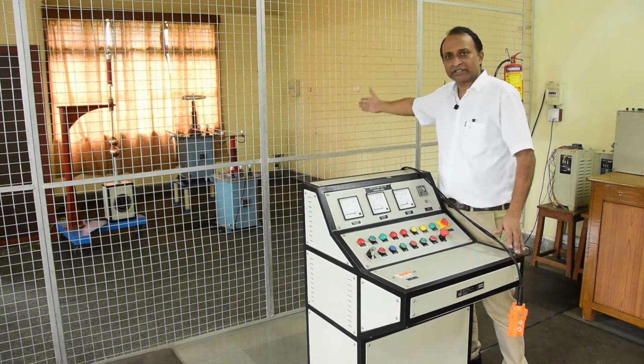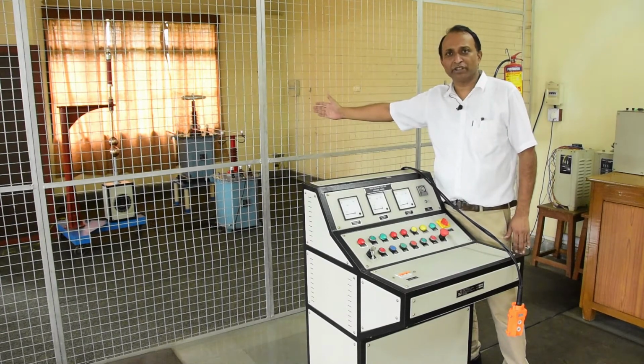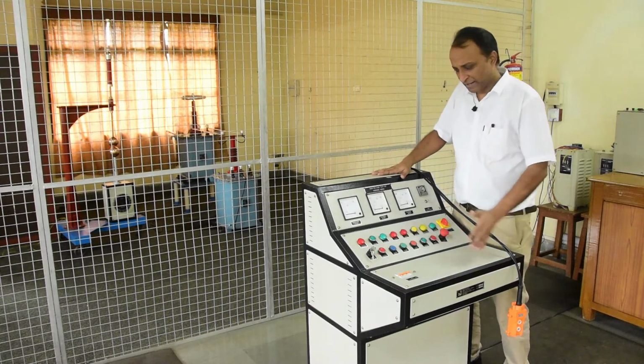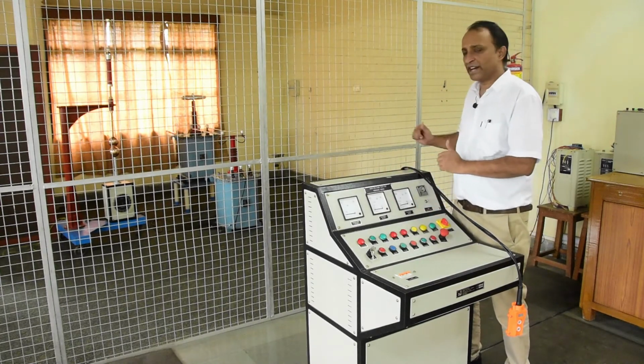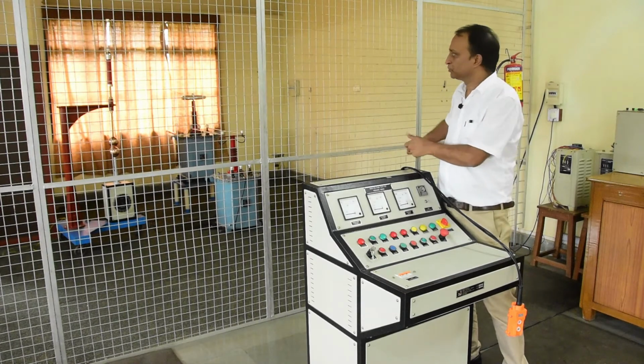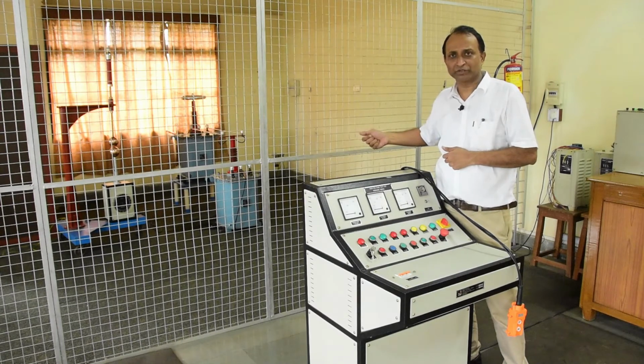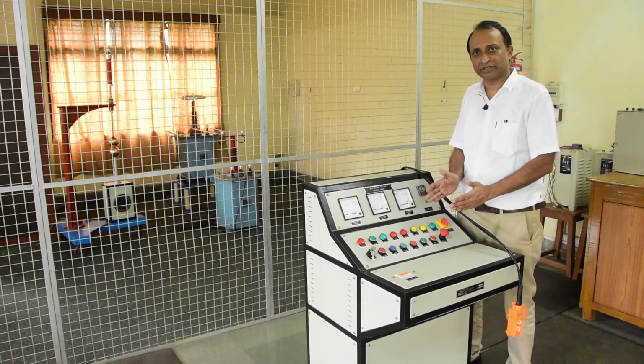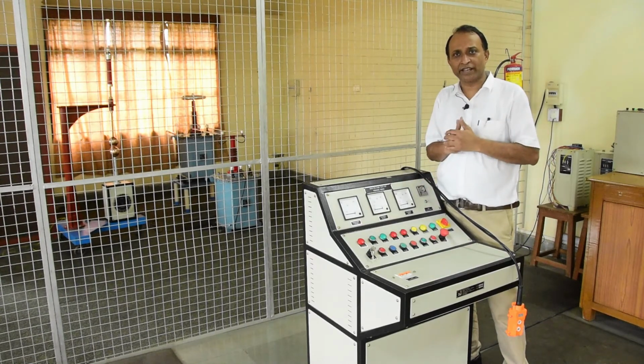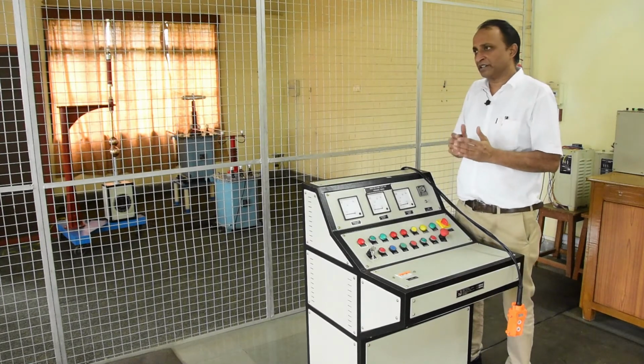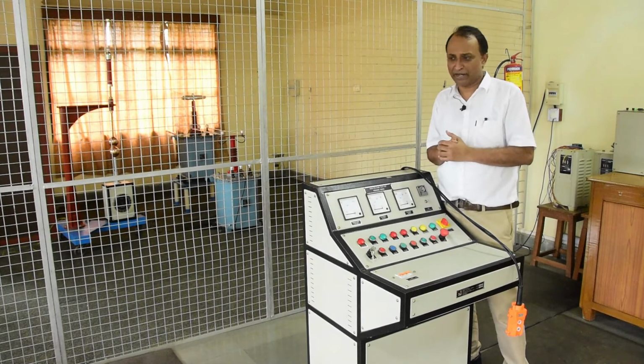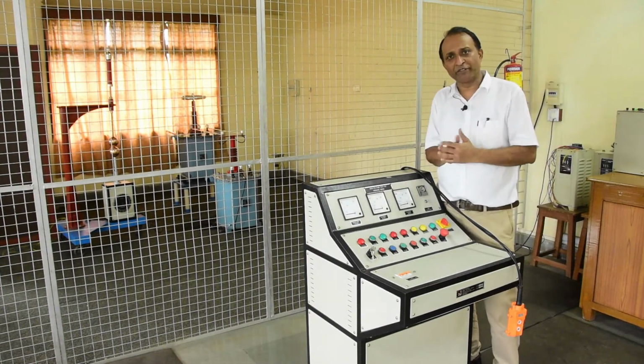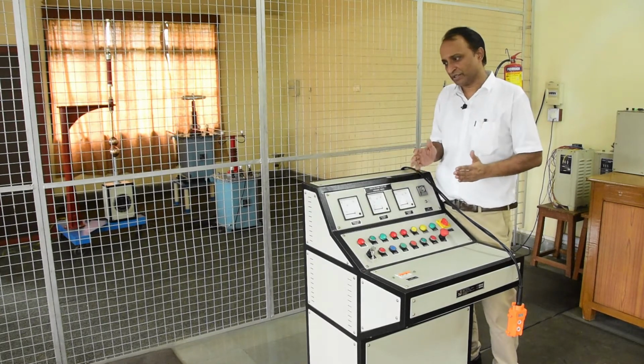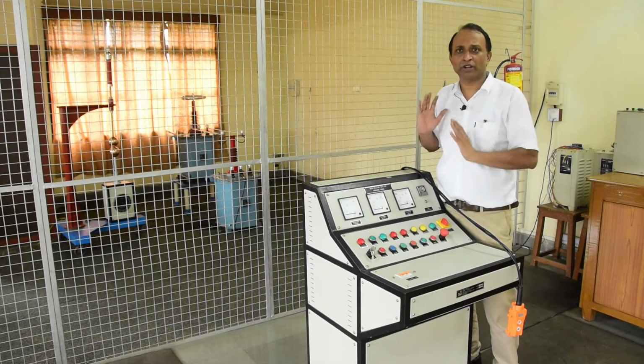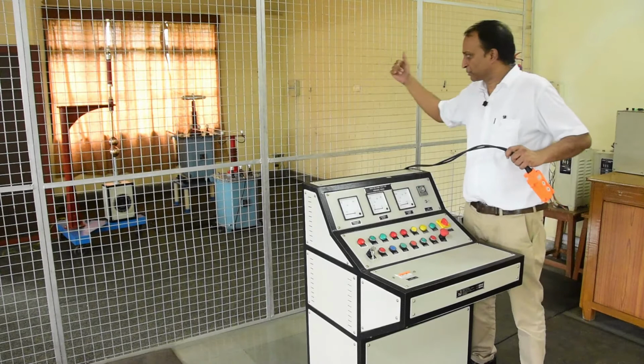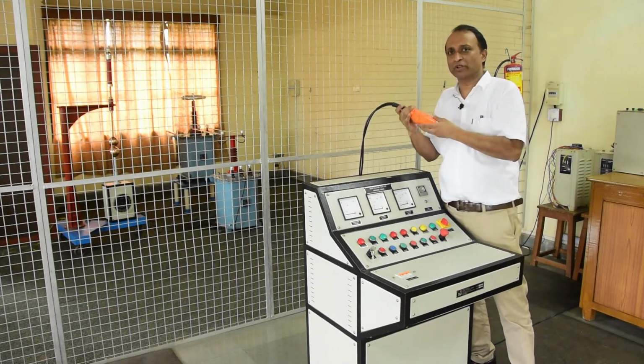The voltage is applied through the cascade transformers, and a standard spacing is set between the spherical electrodes. As the voltage is applied, we observe that at one particular value of voltage there will be a spark across the spherical electrodes. The potential at which the spark occurs indicates the ionization potential of the air gap column, right? These readings are taken repeatedly for the same distance, and if 5 out of 5 readings come out the same, then it is considered that the gap is consistently breaking at that particular potential. The adjustment of spacing between the electrodes can be done using this particular remote.